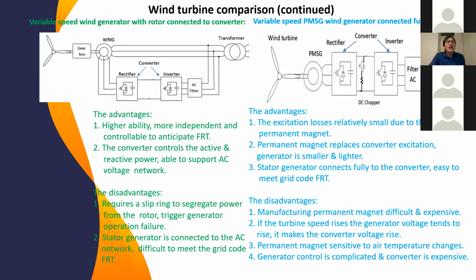The third one is variable speed through the rotor. If we see here, the rotor of the turbine is connected through a back-to-back converter, and from the converter connected to AC, while the stator here is still connected directly to the AC network. The advantage compared to the limited speed turbine is that it is more independent and controllable, and can anticipate fault ride-through because part of the turbine is already controlled by the converter here. So the advantage compared to the previous one is that we are able to anticipate fault ride-through.